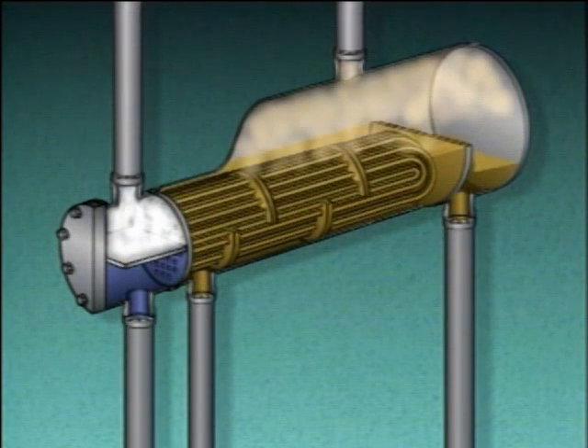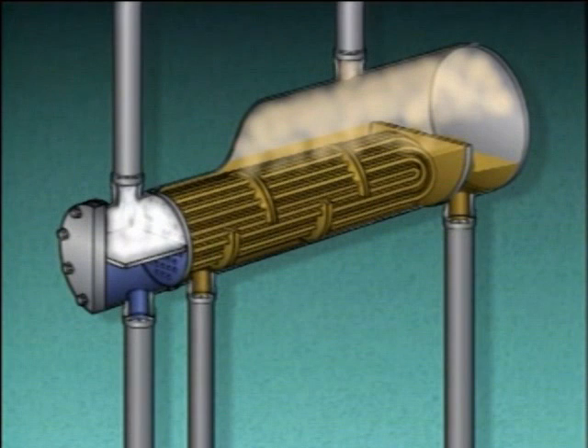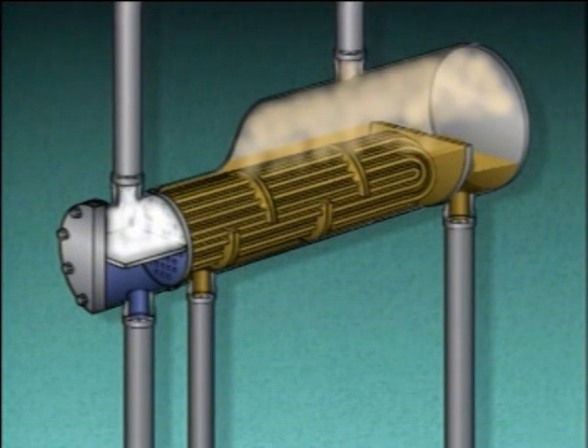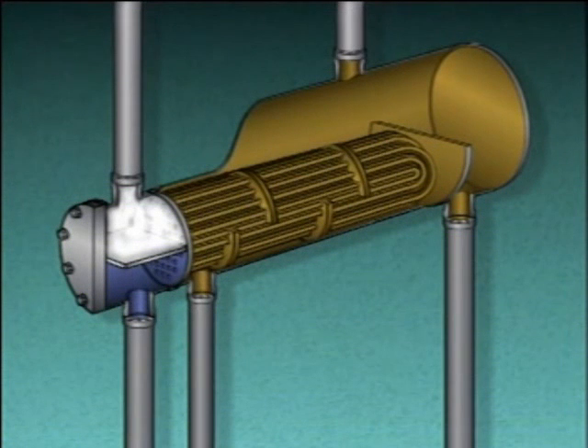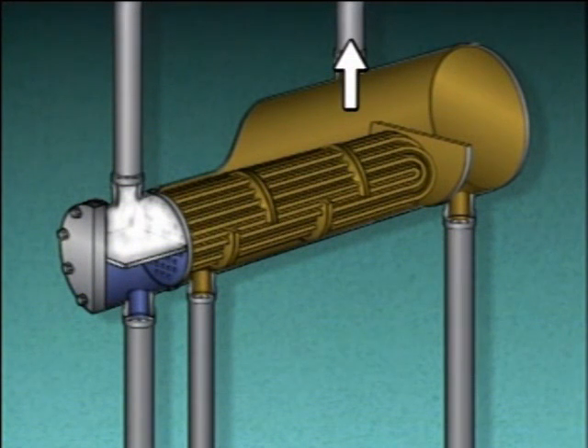On the other hand, a level that is too high can be a problem too. For example, if the level in a kettle type reboiler gets too high, the vapor and liquid will not separate properly and the mixture may flow back into the distillation column.